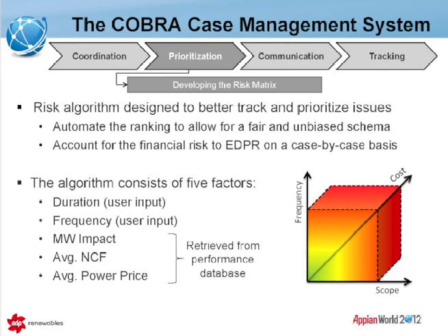What we try to do is we follow a three-dimensional risk matrix here. So we have three different dimensions to it, one being scope of the problem. How much is the problem affecting us? How many megawatts of our turbines are being affected? So what's the extent of the problem? When the event actually occurs, when the turbine is faulted offline, is not able to produce, how long is the turbine offline for? What's the downtime incurred?